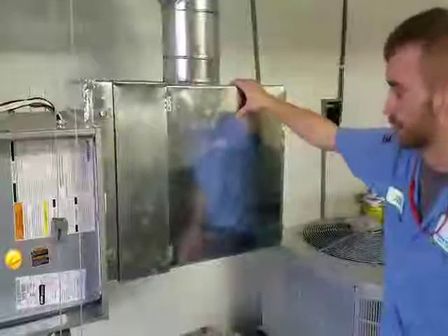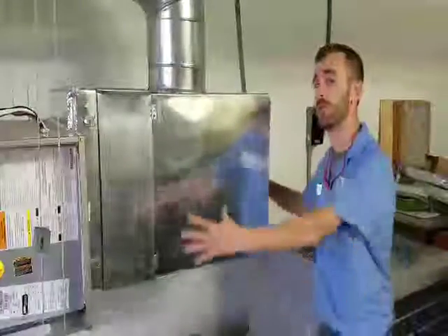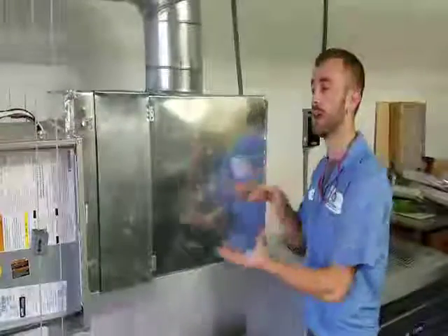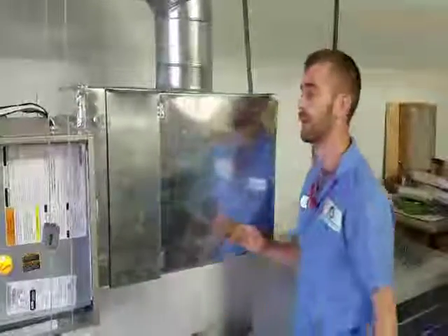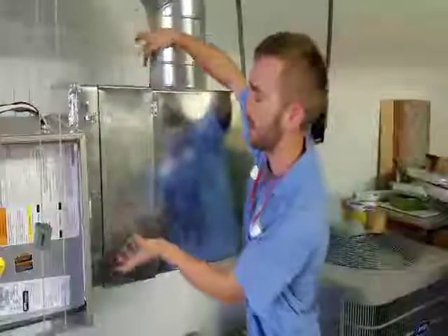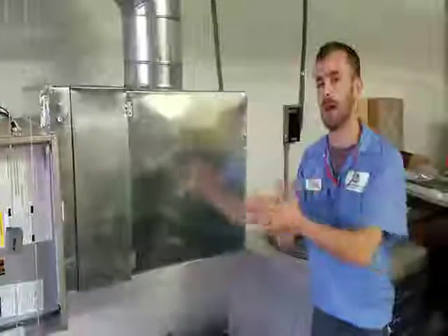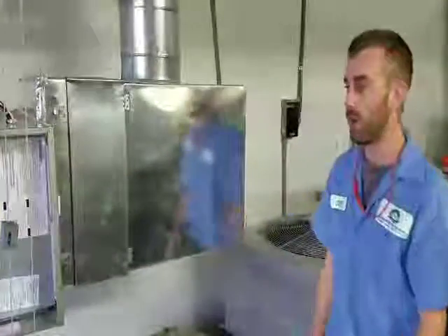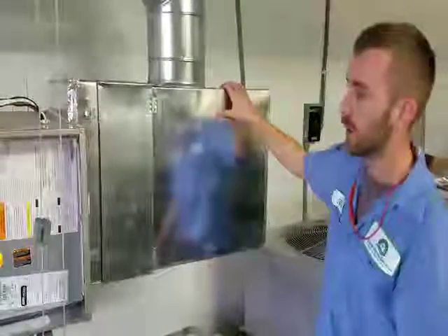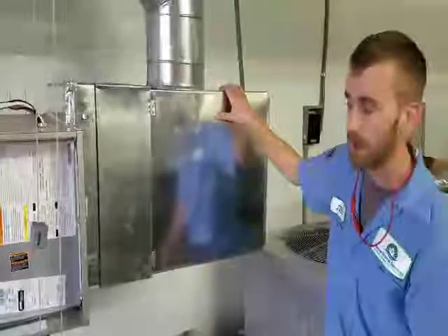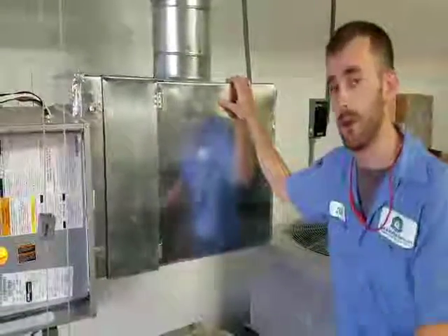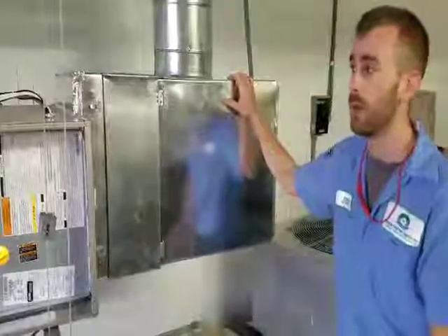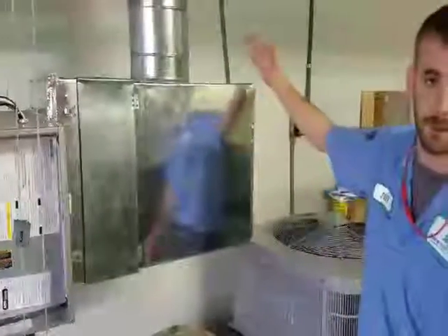See, this is actually a distribution box, and when the returns come to this box, they mix the air and distribute it evenly throughout the furnace. With just a flex tapped to the end of the furnace, there are spots where the heat exchanger isn't getting air across. So if you do not have a return plenum, you definitely want to call a certified technician, have us come out there, run the CO test, and we can design you a return plenum and possibly add a return.